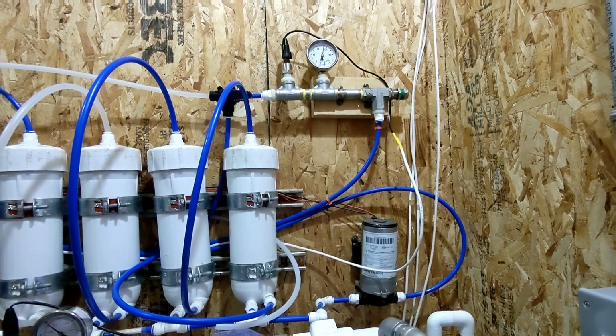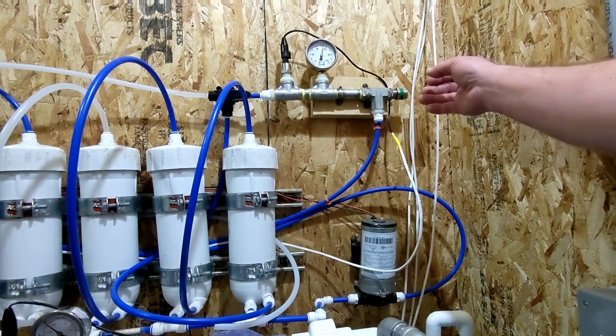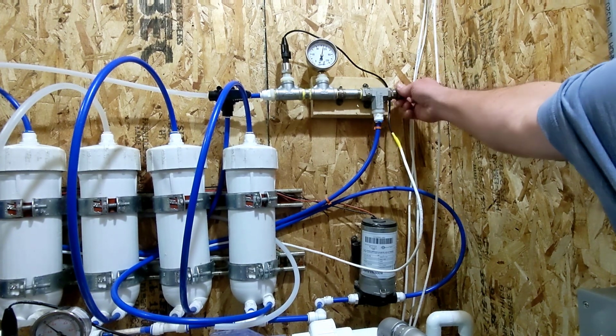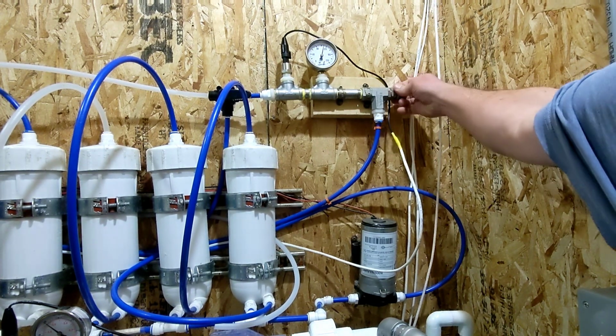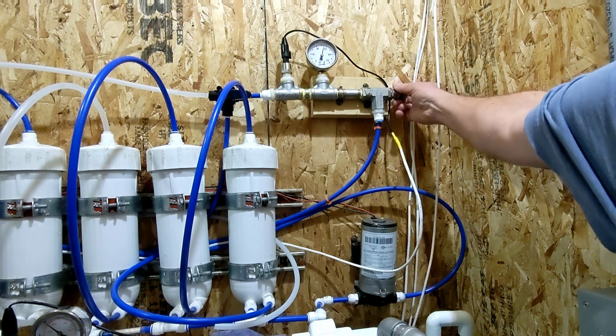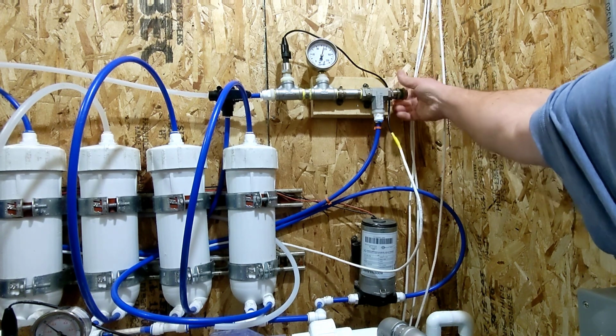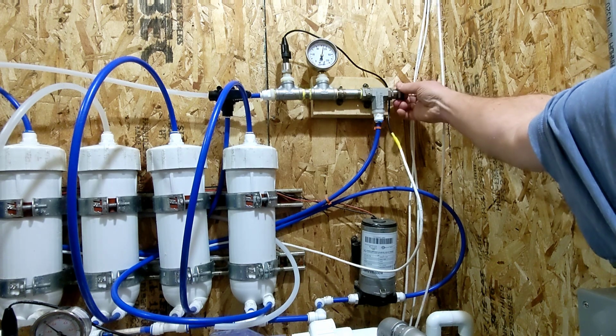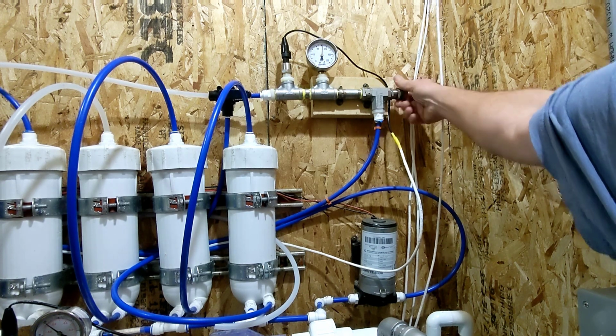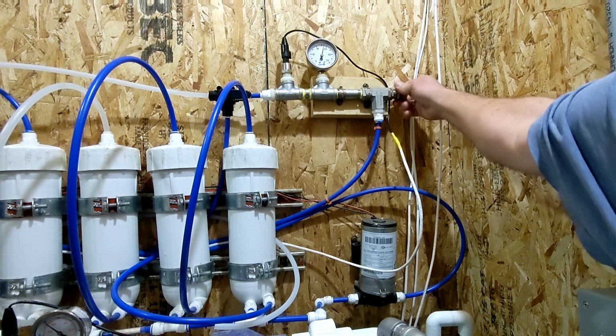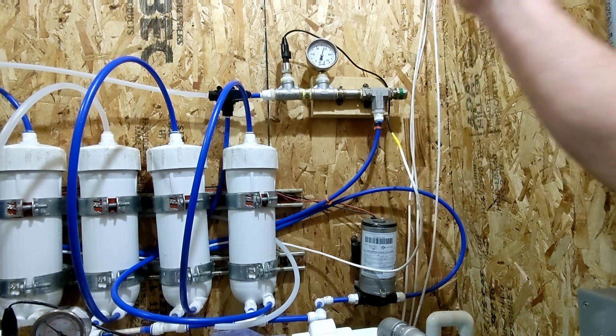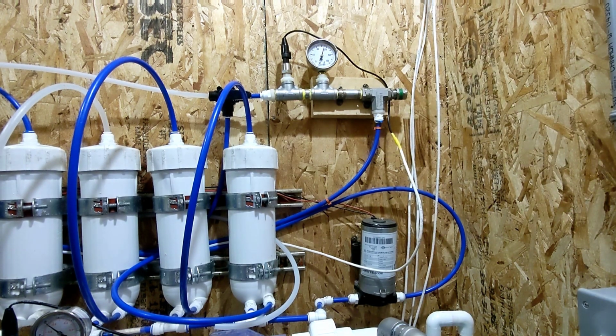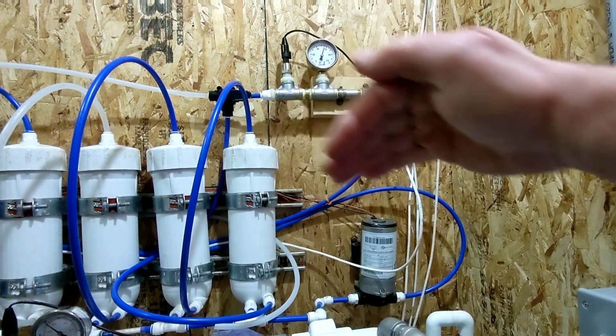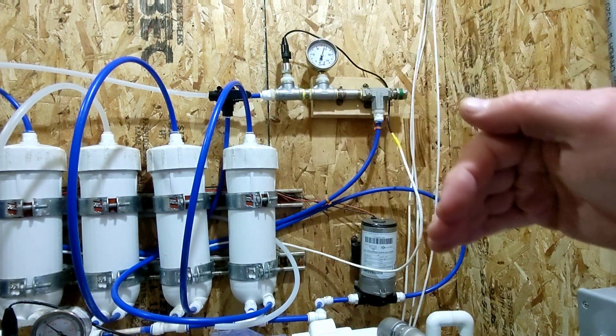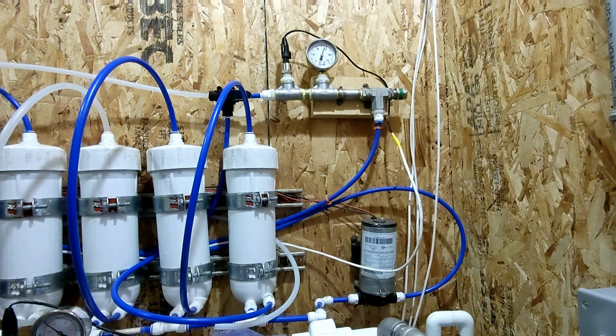Right, that looks like it's about it. So if I want to increase the pressure, I can just turn up the pressure there. You see the pressure's going up a bit, and I can also turn it down a bit. Come on, go down, there we go. So that lets me dial in the exact pressure that I want, and it's running well right now at about 115 PSI. So that valve lets me set the back pressure in my RO system, which increases the pressure across that membrane, and I get more water coming out.